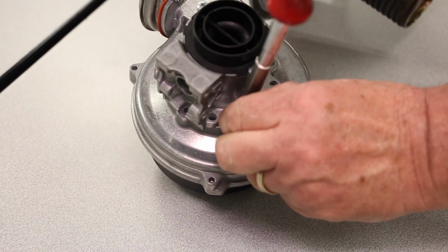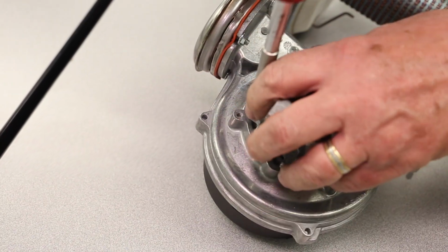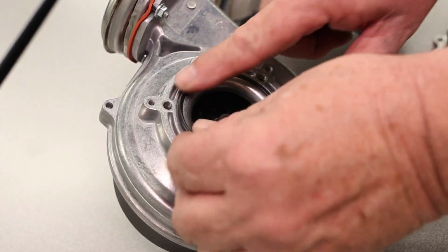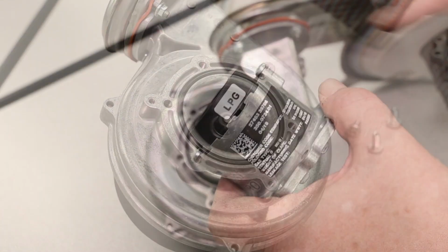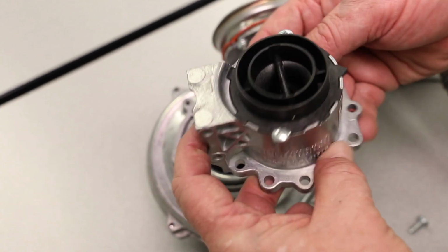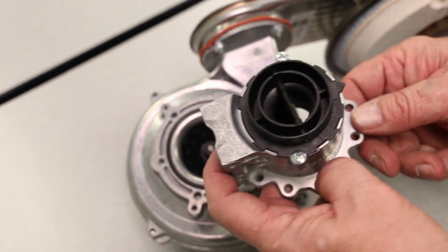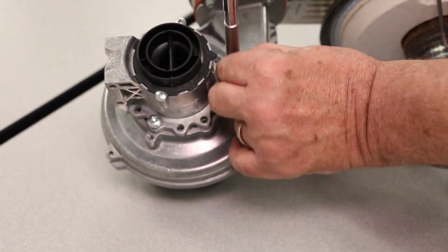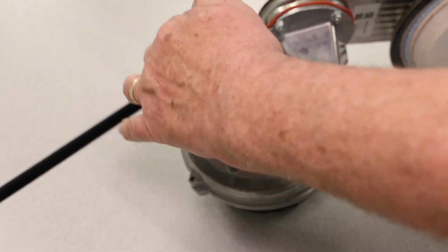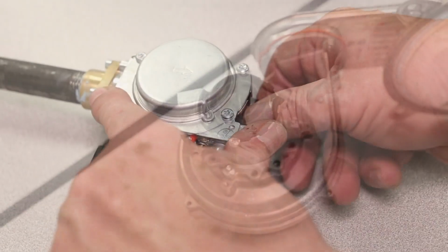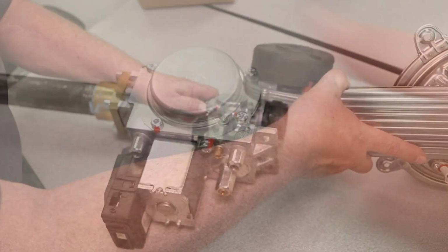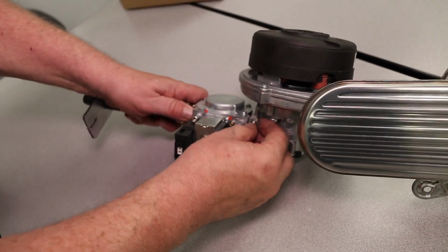Next, remove the 3 Torx screws connecting the original natural gas venturi assembly to the boiler and replace it with the new LP venturi from the conversion kit. Be sure that the O-ring between the blower and the venturi assembly is in place and the arrow on the venturi is pointing upward. Secure the new venturi assembly back to the blower. Verify that the coupling between the venturi assembly and the gas valve is in place. Then reattach the screws on the gas valve.